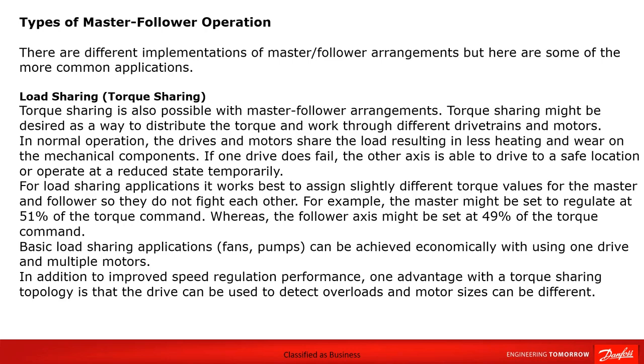However, if one drive does fail, the other axis is able to drive to a safe location or operate at a reduced state temporarily. So you may want to completely stop the application, or like a conveyor, you may need it to run to a certain point before it actually comes to a stop. So in other words, to a standstill.